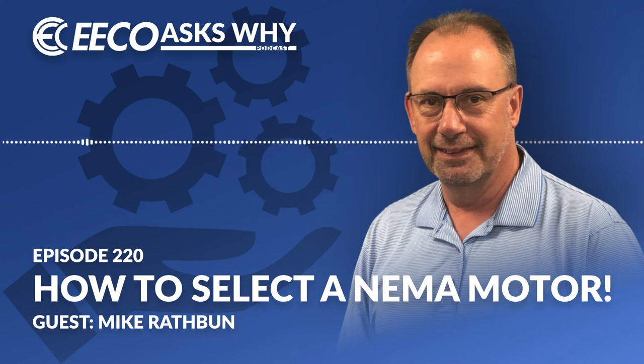You see motors coming from a wide range of manufacturers in a wide range of places around this world. And there's all these different nomenclatures about its capability: it's severe duty, it's inverter duty, it's an 841, it's a totally enclosed fan cooled. There's a lot of different variances there. Having a basic understanding of those, as they apply to your environment more than anything, is the direct correlation. If we start with protection from the environment, an ODP motor, if you think of your old big steel frame large motors from yesteryear, was the ODP design, where you actually had openings in the casing that allowed cooling air to transmit through the motor to provide the necessary cooling.